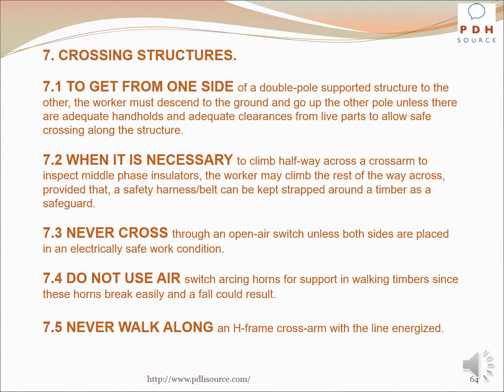When it is necessary to climb halfway across a crossarm to inspect middle phase insulators, the worker may climb the rest of the way across, provided that a safety harness belt can be kept strapped around a timber as a safeguard. Never cross through an open air switch unless both sides are placed in an electrically safe work condition. Do not use air switch arcing horns for support in walking timbers, since these horns break easily and a fall could result. Never walk along an H-frame crossarm with the line energized.